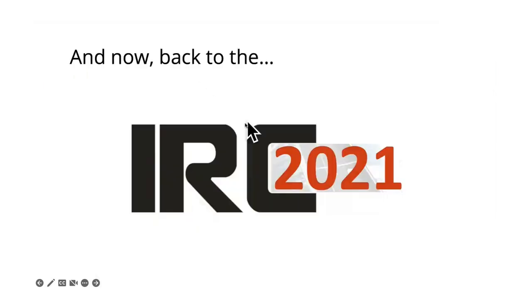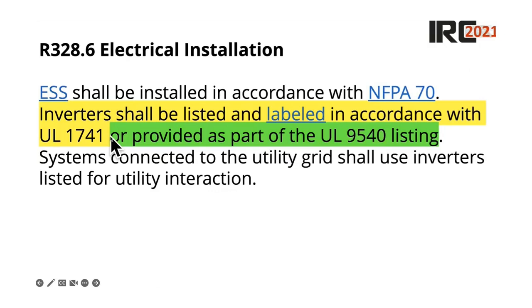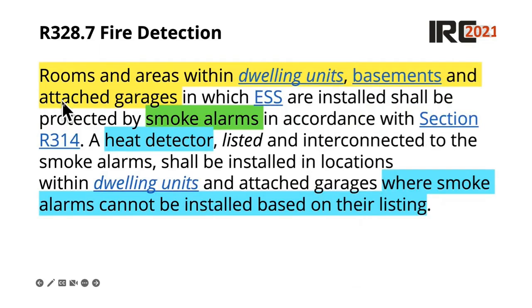Some of these things are similar to the IRC, and so let's get back to the IRC. We need to do things, of course, with NFPA 70, which is the NEC, and interactive inverters have to be listed to UL 1741, a very basic, obvious thing that you see all over through the NEC. This is where it says we do need to have things 9540 listed. However, if somebody is trying to do a big lead acid system, I wouldn't be personally against it. But if you wanted to be really strict with the code, there's no 9540 lead acid battery, so you could give somebody a hard time.